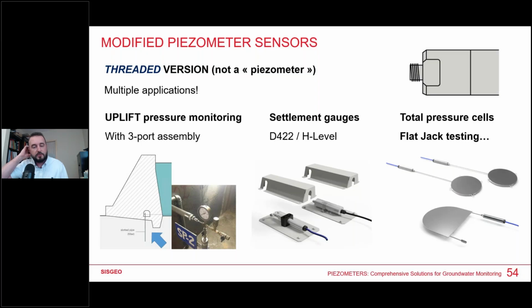And the very last model that we provide is the threaded version. Let's say it's not a piezometer. It's exactly the same sensor as before, but the head is not a filter and not connected to the underground. It's not connected to the environment. It has a thread, and this thread can be used for multiple applications. For example, in the case of gravity dams, concrete dams, we can monitor the uplift pressure. The uplift pressure appears when you have a lot of water behind the dam, and in order to monitor this effect, we install a special piezometer standpipe, which is a closed system because it's linked to a manometer, and then to a pressure transducer.